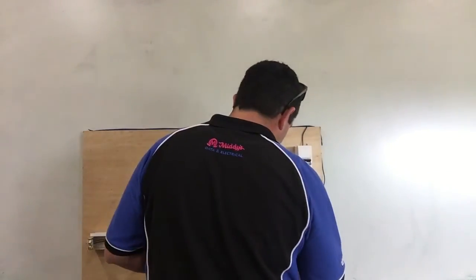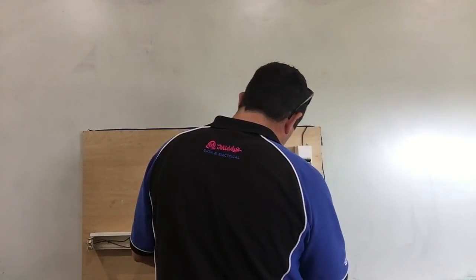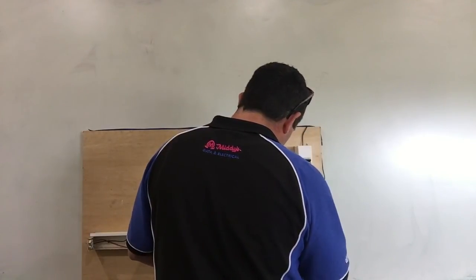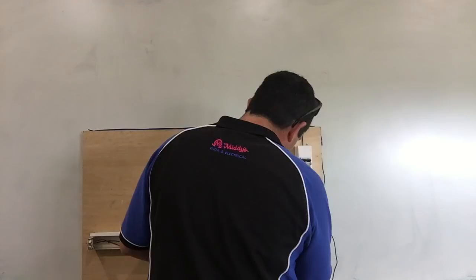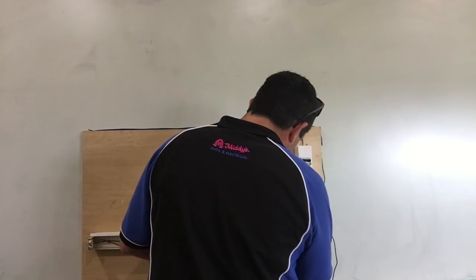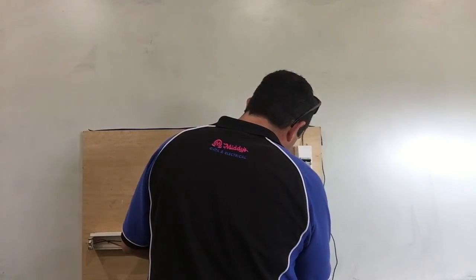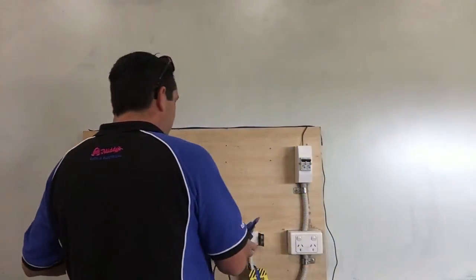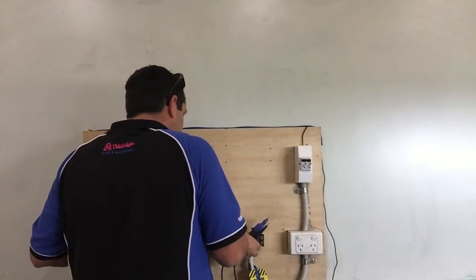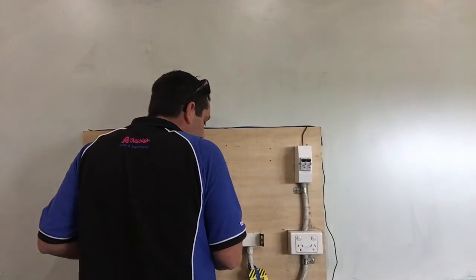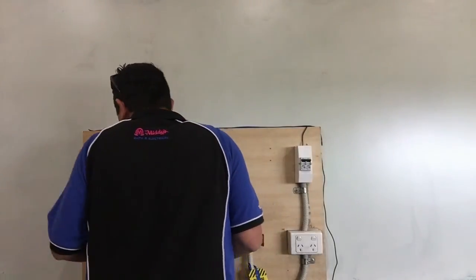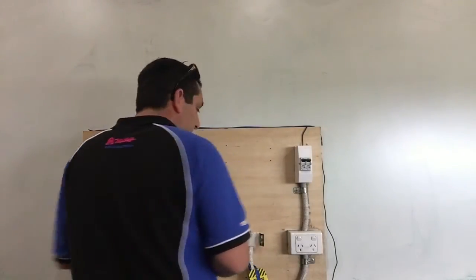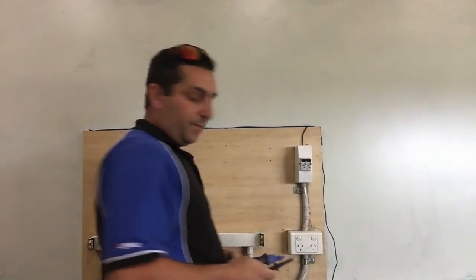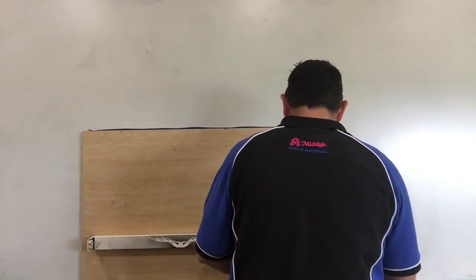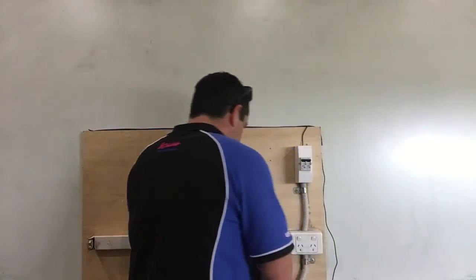We can test from our known earth, active, neutral, earth, and then back at the appliance. Active neutral, active earth, neutral earth. Again, that shows power, so there's no real need to test your tester again. But for the sake of habit, I like to retest our tester. Active neutral, active earth, neutral earth. We can remove our danger tags.